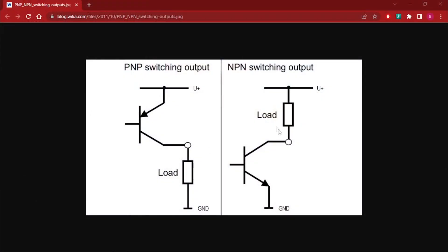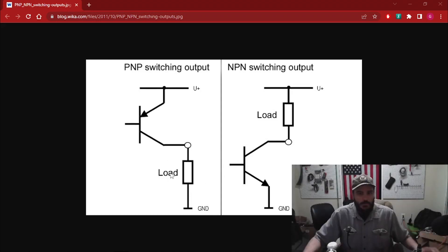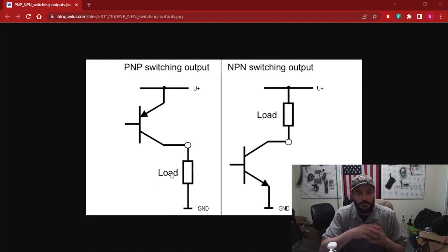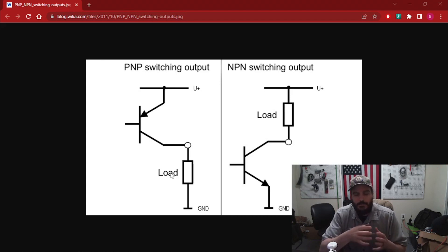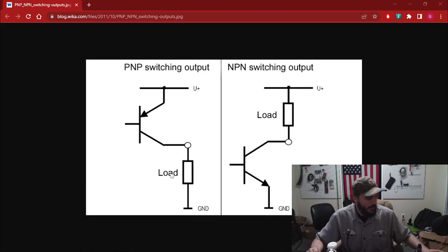It's critically important to remember that a PLC input is in fact a load. It's a tiny small load, but it's still a load. A little light on the front of it lights up and it turns something on internally so the logic knows what to do. It's very important to realize that's a load — small load, but still a load. So when you're wiring your device to a PLC input, the load most of the time actually refers to your PLC input. You could also hook it up to a small relay or other devices, but typically these are landed to PLC inputs.